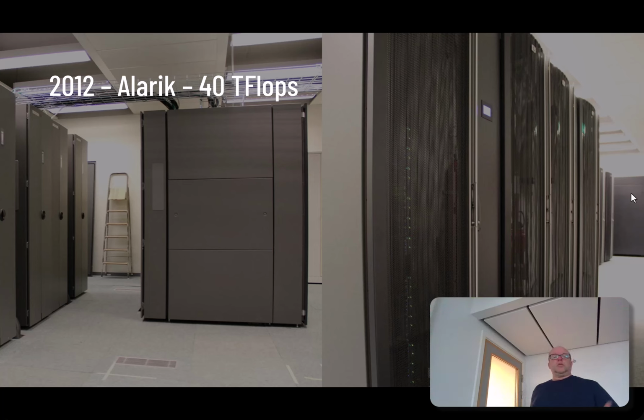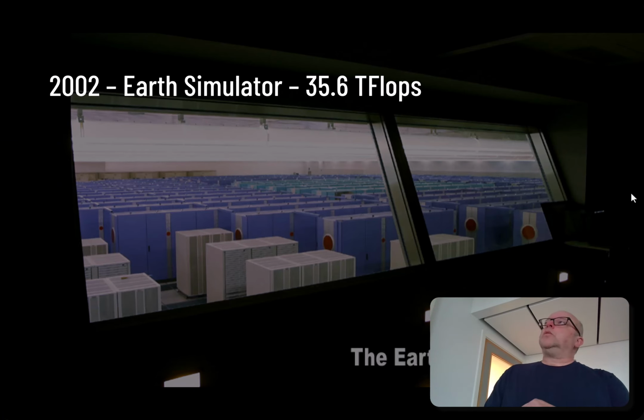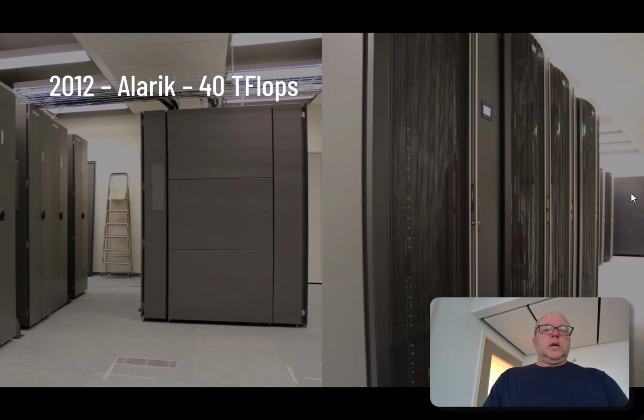So just getting back to 2012, we actually get a teraflop machine, but in a lot fewer racks. If you compare here, in 2002 it was 35.6 teraflops, and here we can get it in 4 racks. So Alarik was one of the first to get into the teraflop range. And it's built around this kind of cooling rack. So you have 2 racks here with computers and then a cooling rack between them that cools the air. It sucks the air in from behind the computers, cools it down and blows it into the front of the machines here to cool them down.